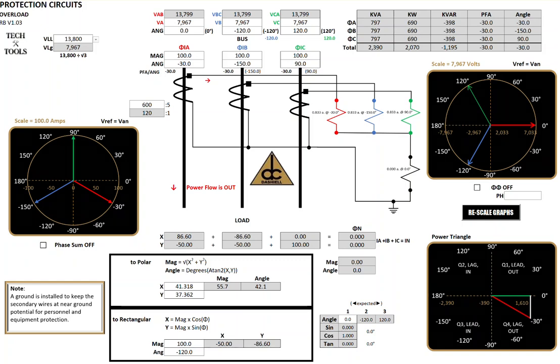So building off of what we did last time, we've got something that looks like a motor load here, induction motor type load. Based on what we discussed, power flow is out. You can see your power flow here, your current flow going into your CTs, and all your CTs reflecting each phase of what they're doing, and summing up ultimately to this value here, which is 0. We could unbalance that a little bit, and we may do that again later.